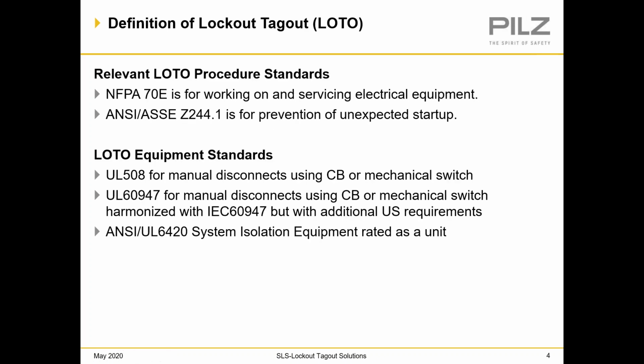As far as the standards themselves, the lockout procedural standards are under NFPA 70E for working on servicing of electrical equipment, and ANSI Z244.1 for the prevention of unexpected startup. As far as equipment standards for lockout, UL 508 covers manual disconnects using circuit breakers or mechanical switches, and UL 60947 covers manual disconnects using circuit breakers or mechanical switches, which is harmonized with the IEC standard but with additional US requirements. And what we're going to talk about today primarily is ANSI UL 6420, system isolation equipment rated as a unit.